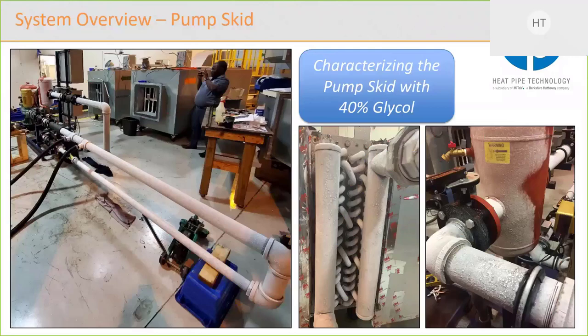Here we've got a few pictures just showing some testing we were doing in the factory. So we recognize that glycol changes viscosity quite substantially with temperature, and with quite a lot of literature search, we're finding that there's no single answer on how that viscosity changes. So we decided to test it ourselves. So in sunny Florida, here we are creating frost in our system. We're actually running 20 degree water through that system and changing temperatures between roughly 70 room temperature down to 20 degrees so that we could see how the glycol changed in viscosity with temperature.